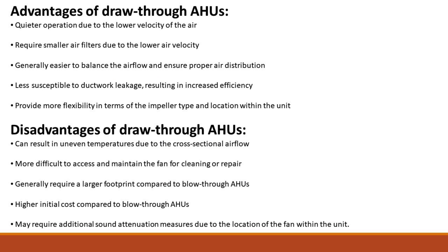Advantages of draw-through AHUs: quieter operation due to the lower velocity of the air; requires smaller air filters due to the lower air velocity; generally easier to balance the airflow and ensure proper air distribution; less susceptible to ductwork leakage, resulting in increased efficiency; and provides more flexibility in terms of the impeller type and location within the unit.